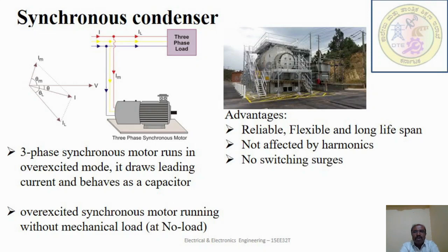A synchronous motor takes a leading current when over excited. Therefore, it behaves as a capacitor. This is the definition: an over-excited synchronous motor running on no load is known as a synchronous condenser. When such a machine is connected in parallel with the supply, it takes the leading current, which partly neutralizes the lagging reactive component of the load. So the power factor will be improved.